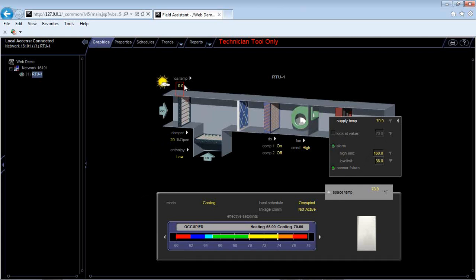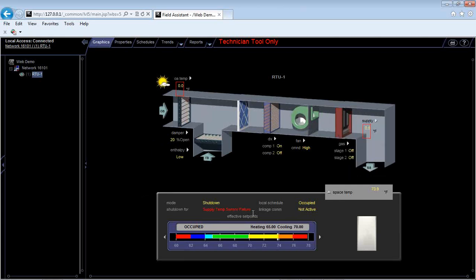Okay, so I just told it I don't have outdoor air, I don't have supply air. Now I'm back in supply temp sensor failure. My fan has a minimum run time on here, so it'll probably run for 90 seconds and then shut off. But the graphic again is all standard, and you can see the fan actually spins and the heat actually turned on.